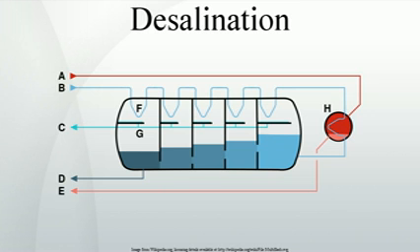The laws of physics determine a minimum energy consumption for seawater desalination around 1 kWh per meter 3, excluding pre-filtering and intake outfall pumping. Under 2 kWh per meter 3 has been achieved with existing reverse osmosis membrane technology, leaving limited scope for further energy reductions. Supplying all domestic water by seawater desalination would increase U.S. domestic energy consumption by around 10%, about the amount of energy used by domestic refrigerators.